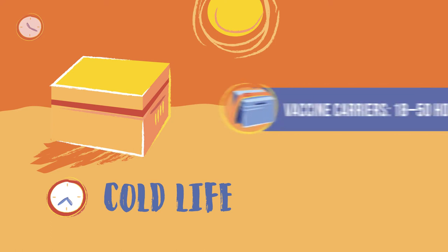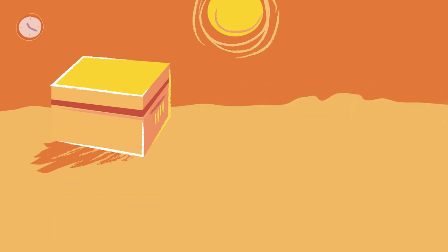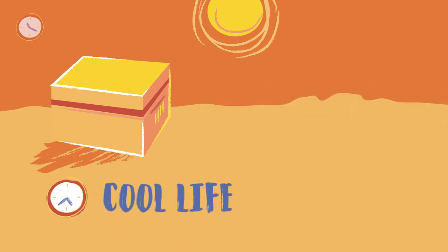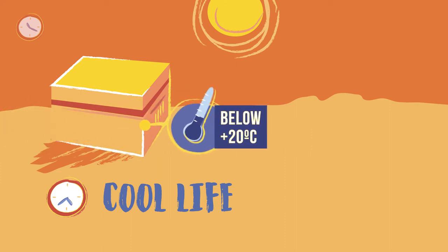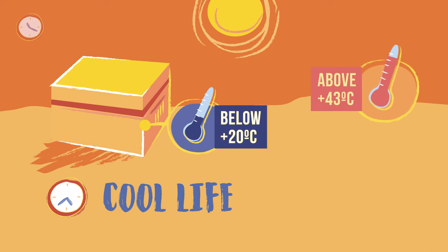Vaccine carriers have a cold life between 10 and 50 hours. A vaccine container's cool life is how long the closed container lined with cool water packs that have been stored in a refrigerator can maintain a temperature below 20 degrees Celsius while at a constant ambient temperature of 43 degrees Celsius.